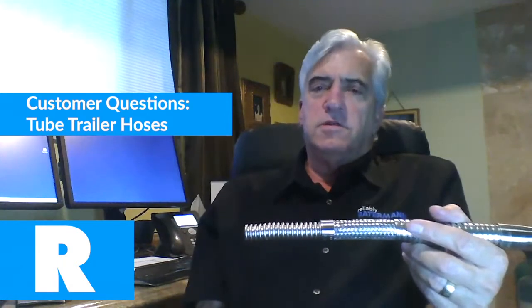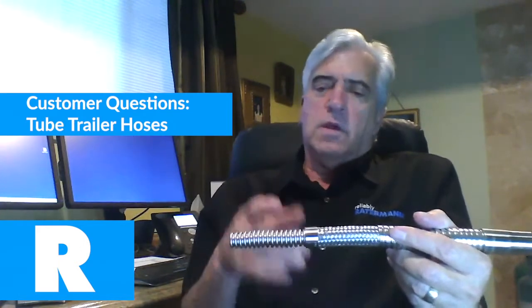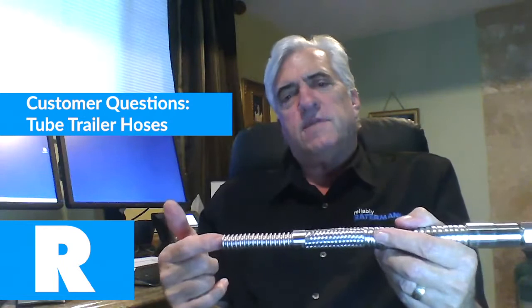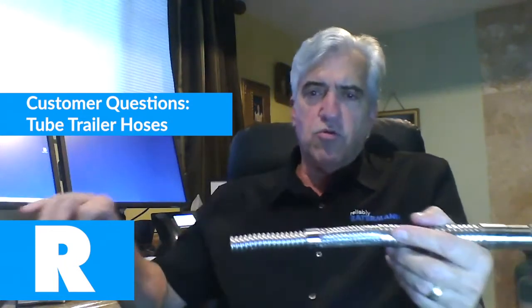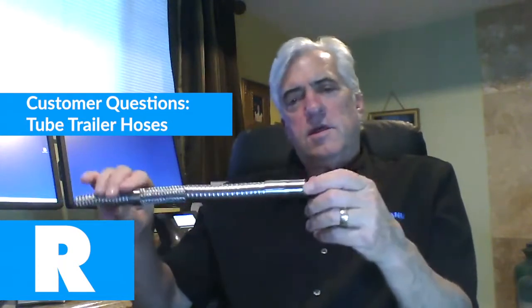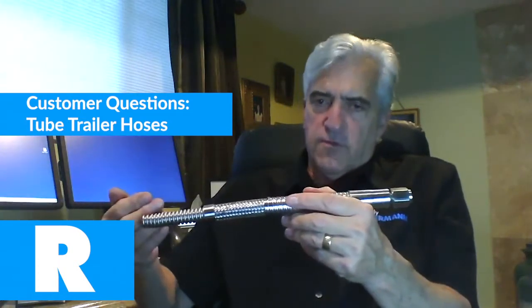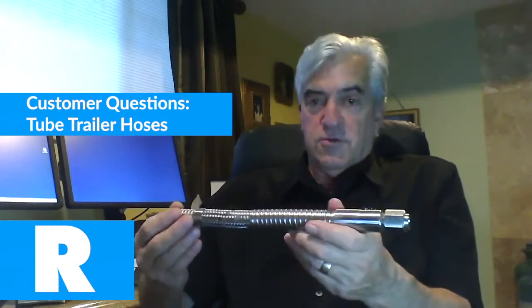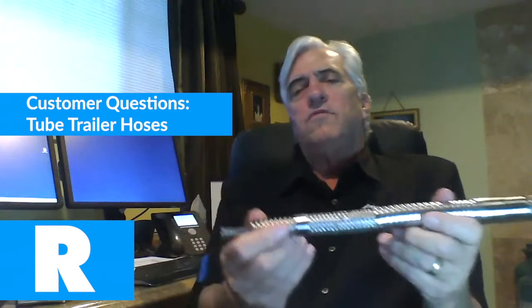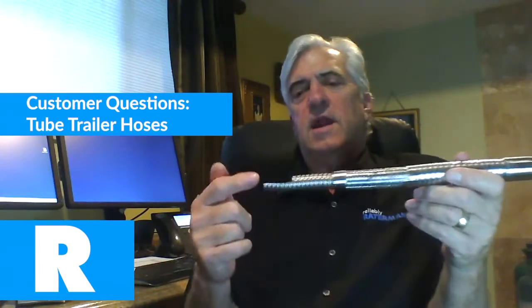What we did as an industry to combat this is basically we keep the stainless steel inner core, but we insert a Teflon liner. And that liner gives us a smooth bore. And basically, that smooth bore allows us to put through higher flow rates without any issues.